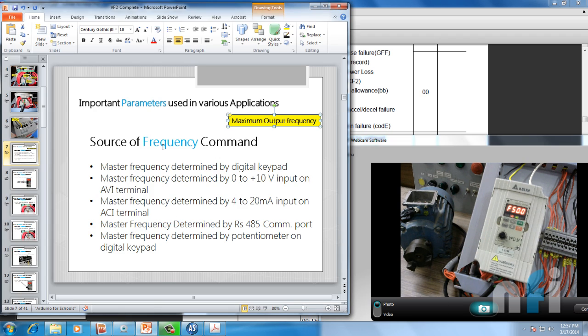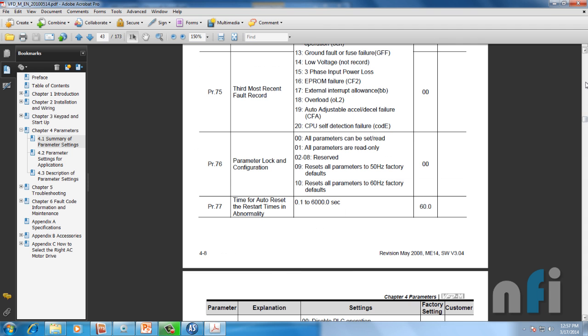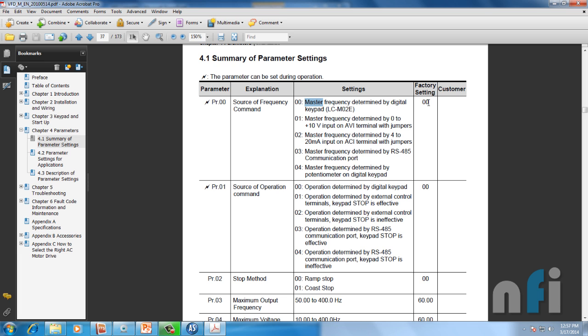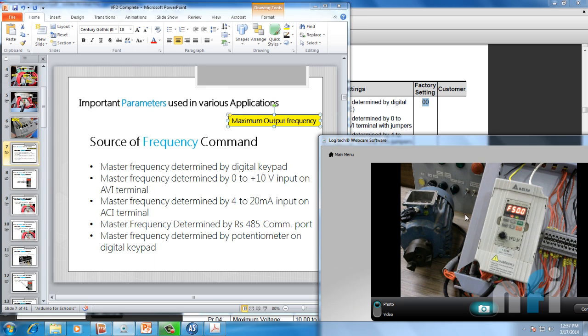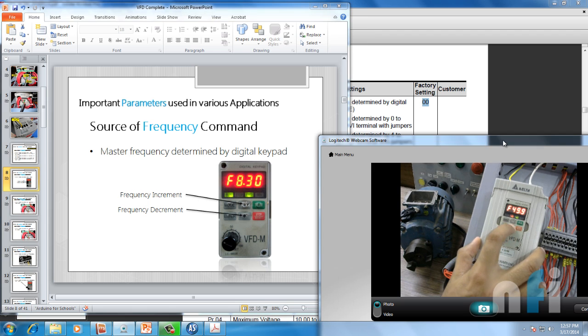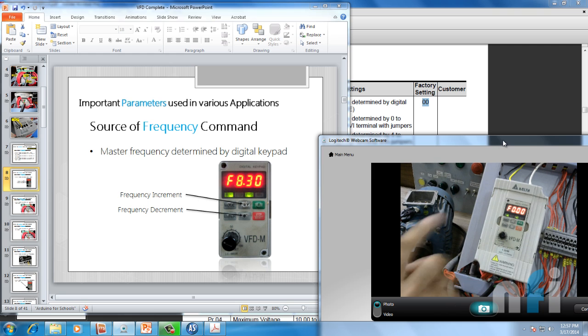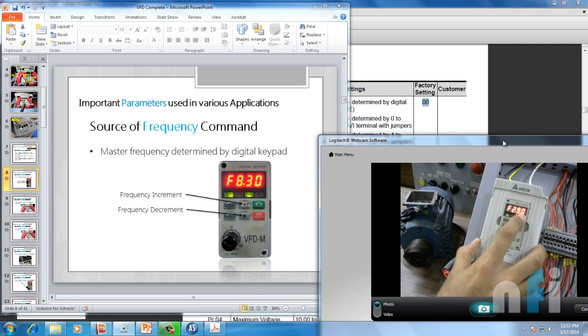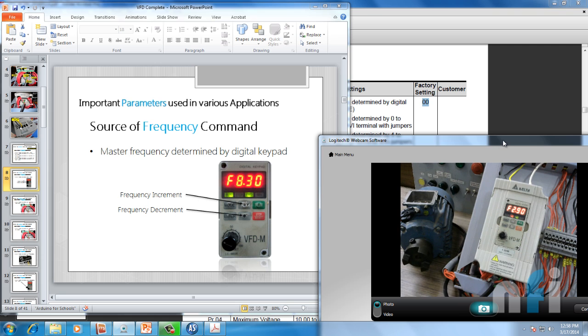Going back to frequency — let's move to the first parameter: source of frequency. Parameter 00 is source of frequency; value 00 means master frequency determined by digital keypad, which is the factory setting. Right now it's at 50 Hz — I can decrease that using the keypad commands. When I press run, the motor is running but frequency is zero. I can increase the frequency and the motor will start — for example at 6 Hz — and I can decrease using the decrement. That's frequency control by digital keypad.